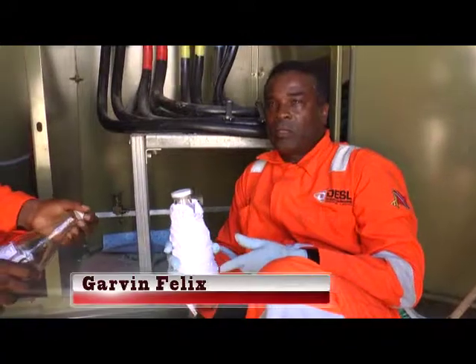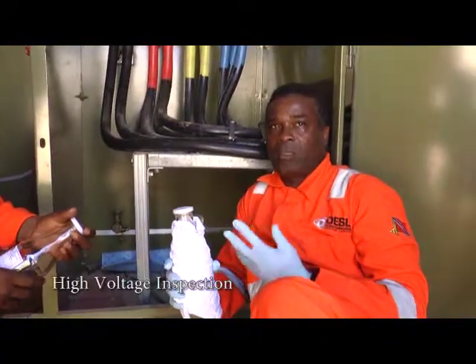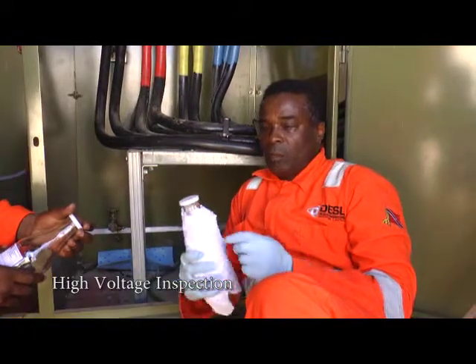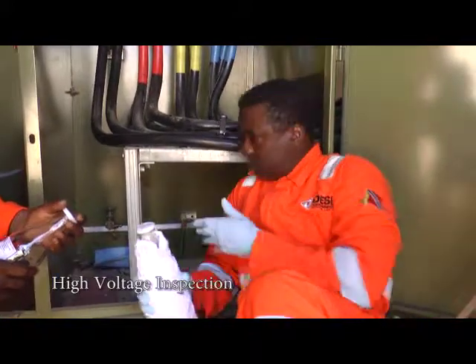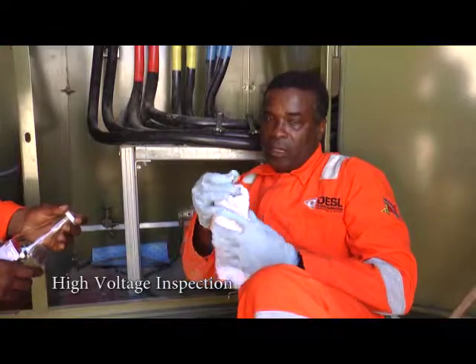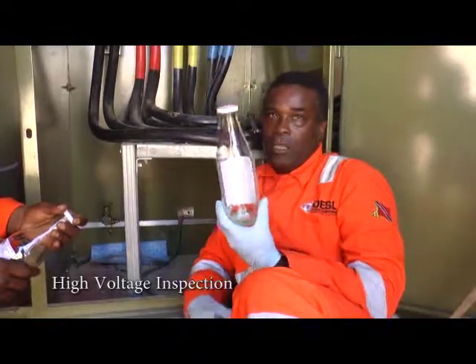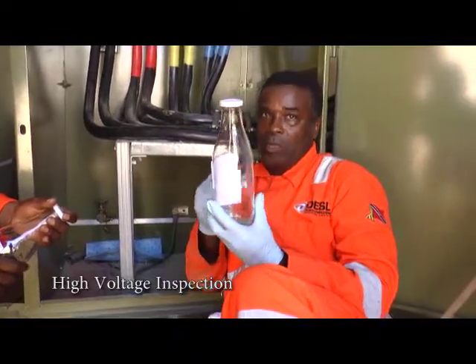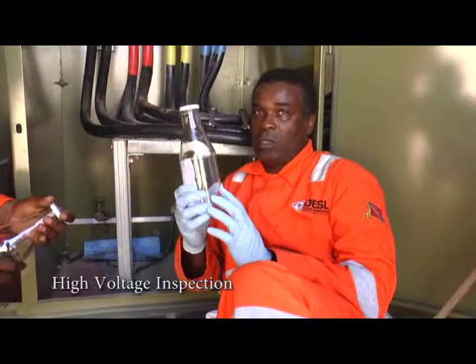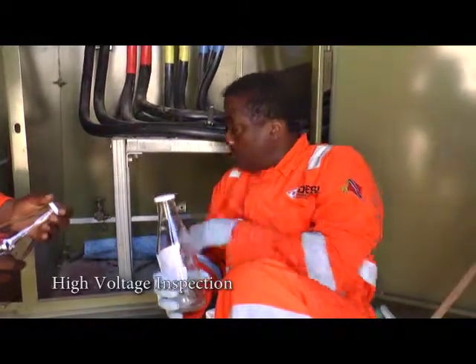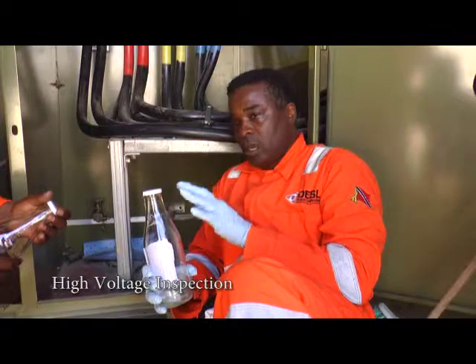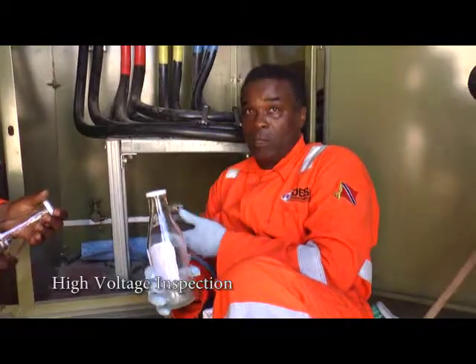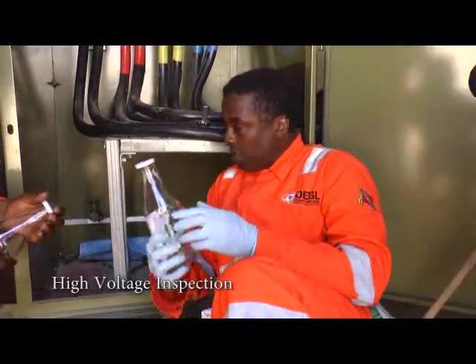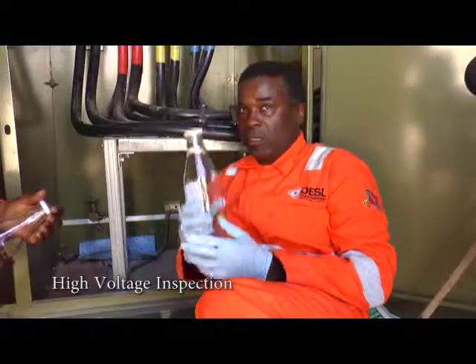Do an oil sample on this transformer. Today we're doing an annual maintenance on this transformer. Normally we just take our oil sample, and this is the bottle here. We rinse out the bottle and bake it at a certain temperature. After it's baked, we cool it, and when we go in to take an oil sample on the transformer, we just use this bottle.